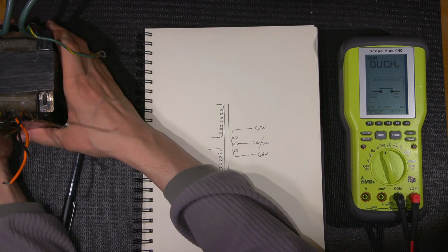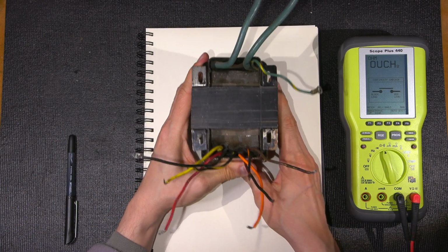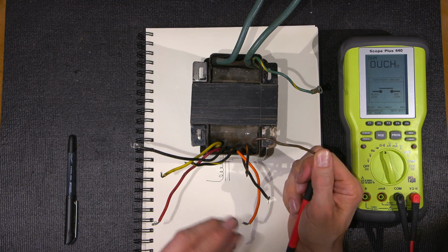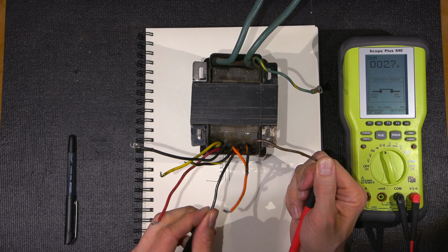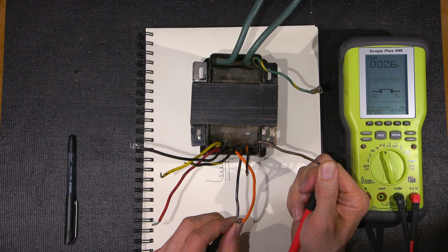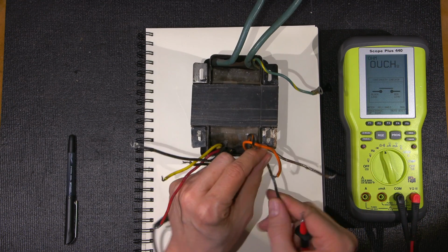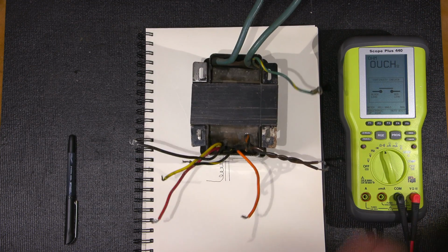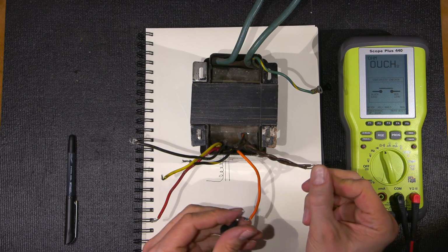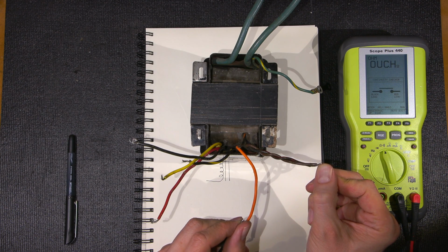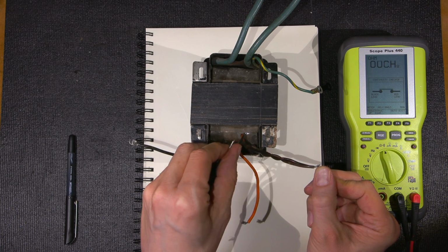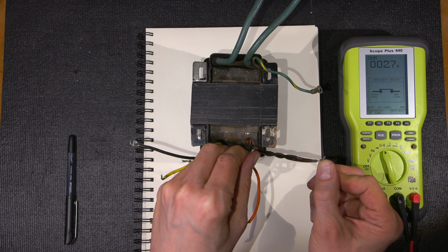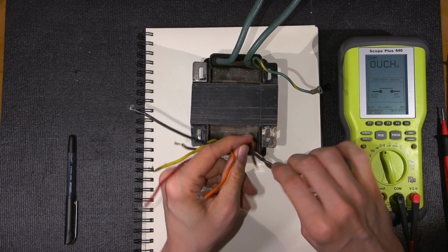Pretty simple, right? So let's just pick one wire. Let's pick the brown. This one, just because. So if I touch a striped lead here, I have a resistance reading. So what I want to do now, because this is one winding, is just twist these two together like so, to organize this. So from brown to orange is no connection. From brown to black with an orange stripe is a connection. So I'm already seeing a pattern here, stripe leads.